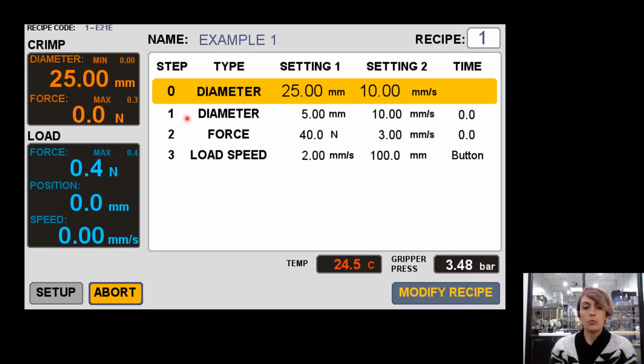I've programmed in step 1 to be a diameter step of 5 millimeters. So this is just a rapid movement step. I've kept it at 10 millimeters a second, and its purpose is to come from 25 millimeters down to 5 millimeters quickly, so I don't have to wait for the machine to move all that distance. Then I've programmed in a force step. Again, this is still a compression step, but now rather than controlling the diameter, I'm controlling the force, and I'm telling the station to crimp on my stent with 40 newtons of force.